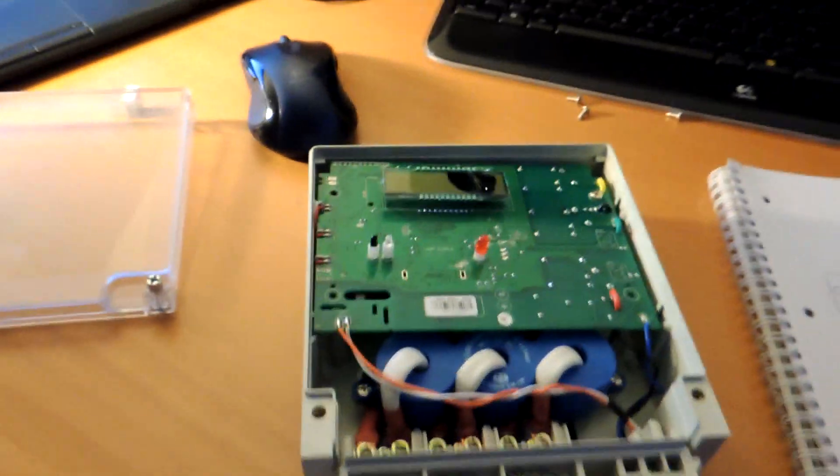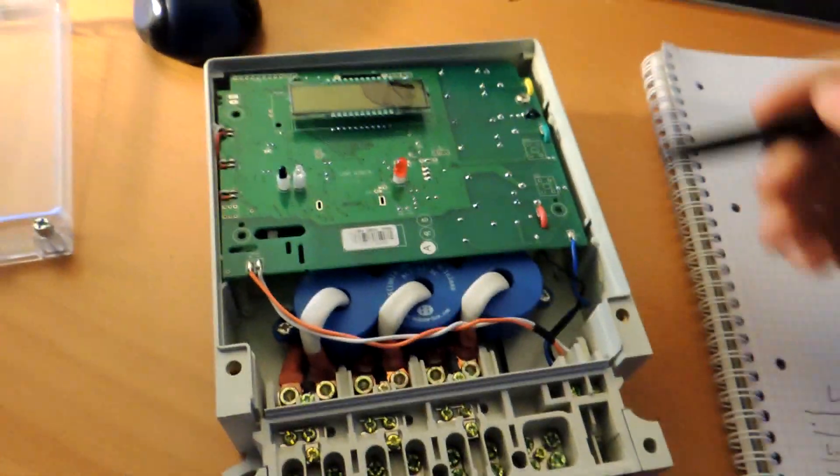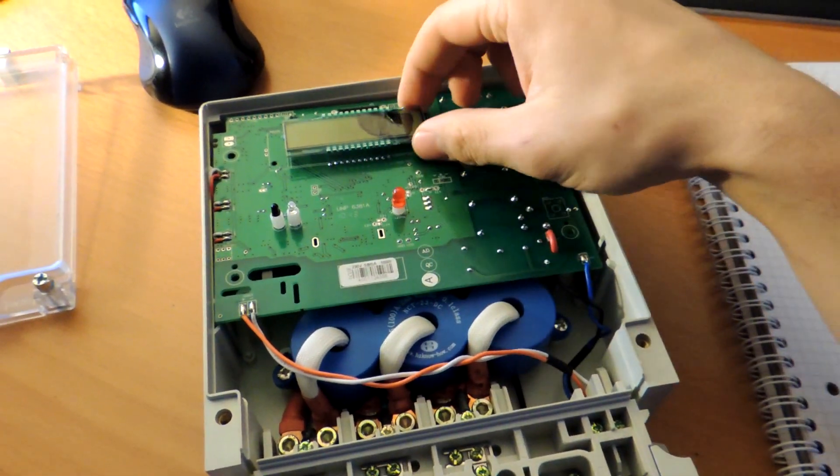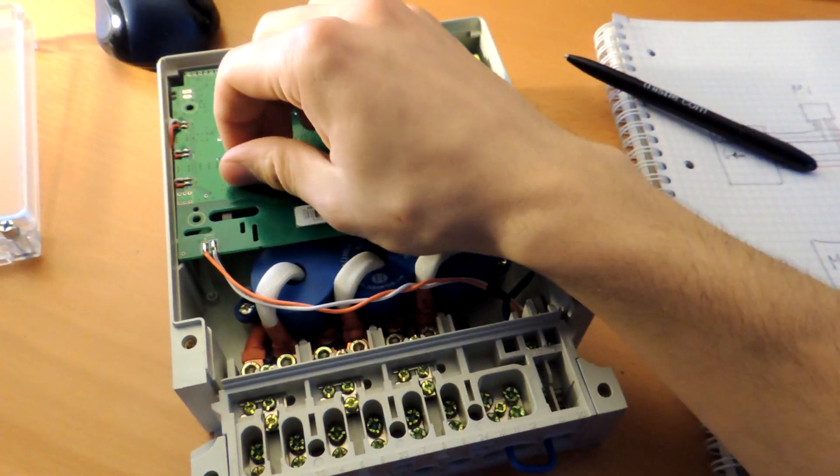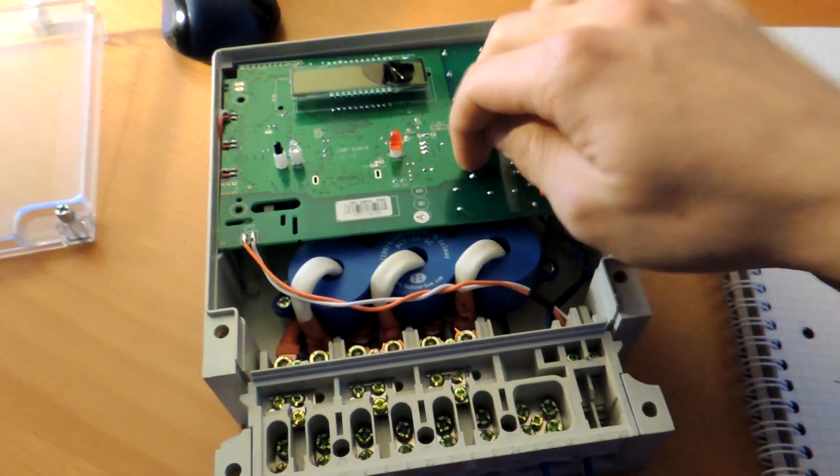The use of the shunts there, because you can unscrew them and slack them off, is that normally in Switzerland, each year you have to take some meters off the market from the client's house to calibrate them. And if they're way off mark or track, you have to replace all the meters from all the clients, all the model.